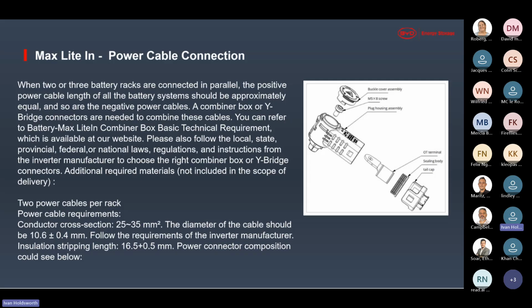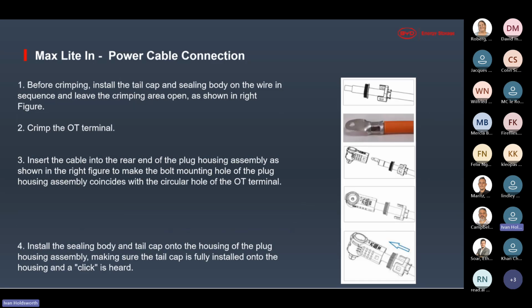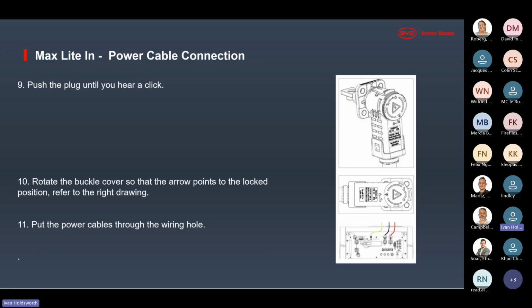Here we can see the power connector that was demonstrated in the video, and the various steps that are taken to install it. It is a lock connector, so if you are struggling to remove the connector, those connections do rotate, and there's also a lock that prevents the tab being operated. So there's a rotary device on the top of that connector, which will prevent the tab being open. And once you've pulled that tab, you should be able to pull the connector off. If that connector is still locked, you'll have to rotate that connector to unlock it. It's always important not to pull too hard, to make sure those connections can be safely removed.